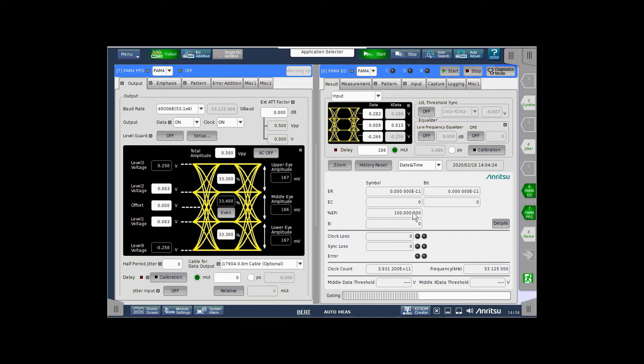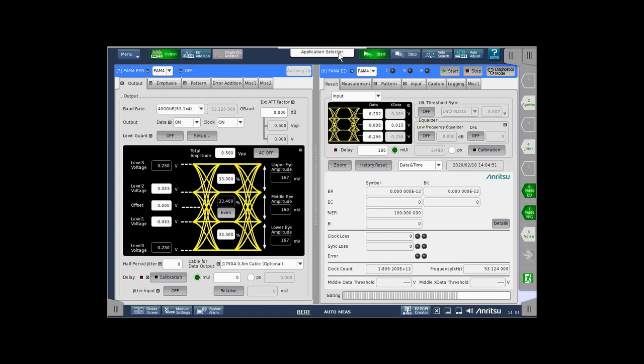From this point, you can look at additional details provided by the error detector, which includes a breakout of the MSB and the LSB, as well as the symbols and the symbol errors that you may be encountering. And that's it. Those are the steps needed to put the MP1900 into a PAM-4 error-free loopback from an initialized state.